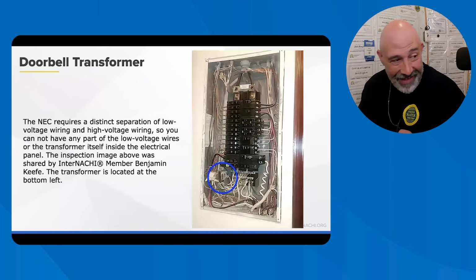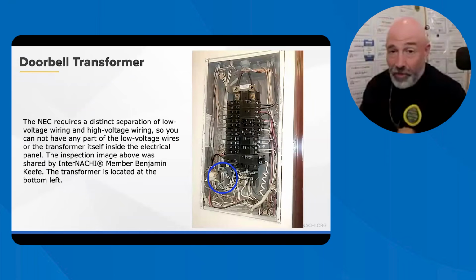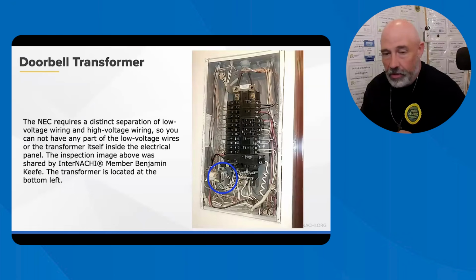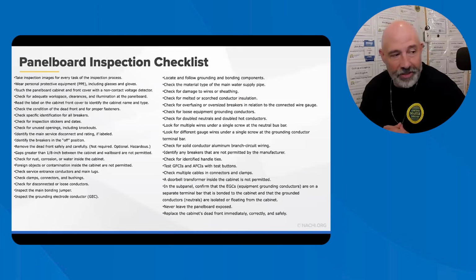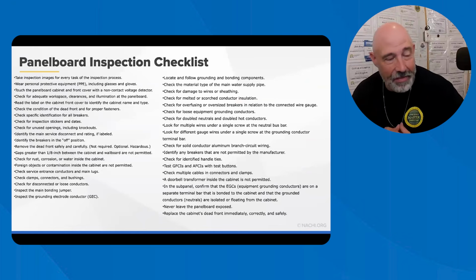The doorbell transformers, anytime they're inside the panel, they have to be outside the panel. That's why you'll see it on top of the breaker box. So call those out. Say, hey, look, you can't have low voltage and high voltage in the same area. They don't get along. It's like having children in the bathtub with you when they're in their teenage years. You don't want that. I shouldn't have said that. That's wrong. So that's kind of how it works.